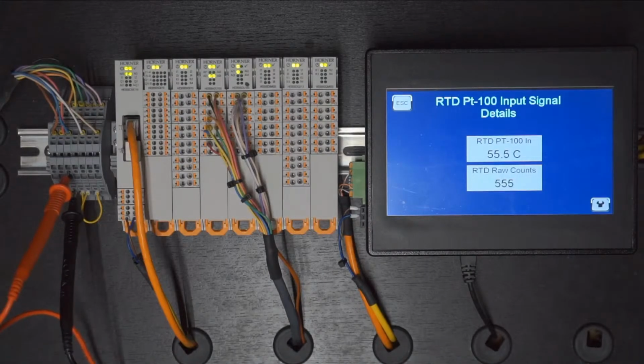Now, the reason it's taken so long is it was basically an open circuit. So it was way up there at full range, and it's taken a while to get down close to 50. And again, my unit's not factory calibrated, so I'm not really all that close, to be honest. It's getting there slowly. Let's go ahead and switch it up to 500 degrees and then see if we can get up in the neighborhood at least. Yeah, we're getting up in the neighborhood. Again, this unit could really use some factory calibration on the RTD range for sure.